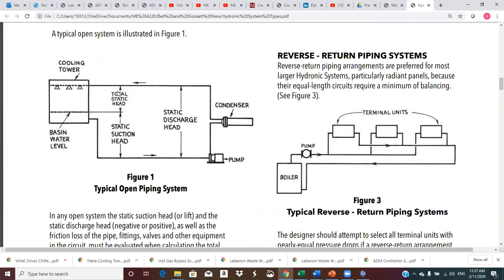And so it doesn't matter what the flow rate through the system is, the pump always has to overcome the static head. If the pump can't overcome the static head, then there can be no flow. If it's not strong enough to push water up, say that's 30 feet and you only have 20 feet of head developed by the pump, there's no way. It's not strong enough to take it from that level and push it up there, you'll have no flow.